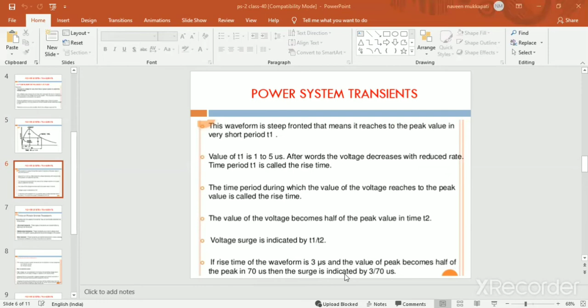If the rise time of a waveform is 3 microseconds, and the value becomes half of the peak in 70 microseconds, then the surge is indicated as 3 by 70 microseconds. The rise time means T1, that is 0 to the crest point, equal to 3 microseconds, and the value of the peak becomes half of the peak in 70 microseconds. Therefore it is indicated as 3 by 70 microseconds. This is called the rise time or the peak time.